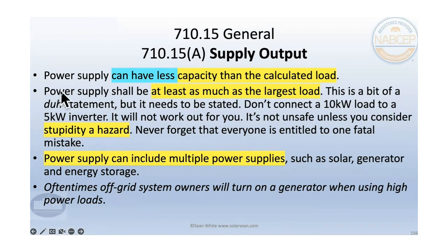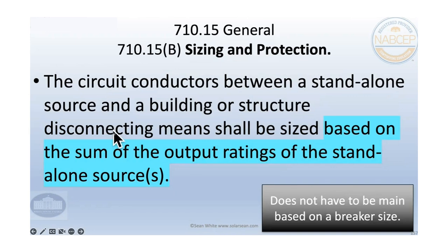So for instance, my brother has a system up in Alaska where it's got PV, an inverter, and a generator. And there's certain loads that he can only operate with the generator, and that's okay to do. And it would just be kind of stupid, that something wouldn't work if you had a 10 kilowatt load and only a 5 kilowatt inverter, because it would never turn on. It would just automatically, the reset button would come on, or maybe the surge could handle it for a second and then it would turn off. And so we don't need to supply the whole calculated load.